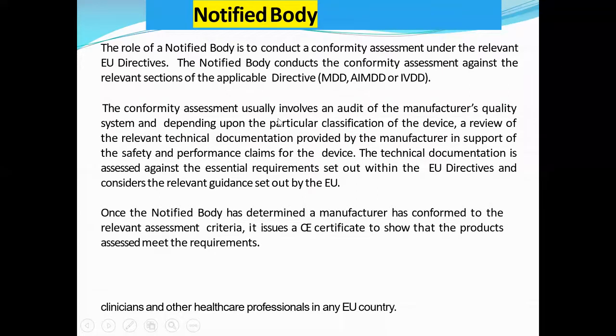So the conformity assessment usually involves an audit of the manufacturer's quality systems, and depending upon the particular classification of the device, a review of the relevant technical documentation provided by the manufacturer in support of the safety and performance claims for the device. The technical documentation is assessed against the essential requirements set out within the EU directives and considers the relevant guidance set out by Europe. Once the notified body has determined a manufacturer has conformed to the relevant assessment criteria, it issues a CE certificate to show that products assessed meet the requirements.